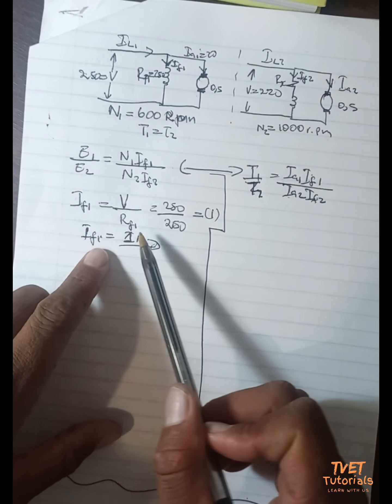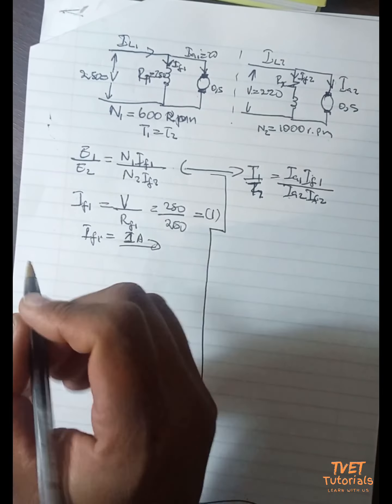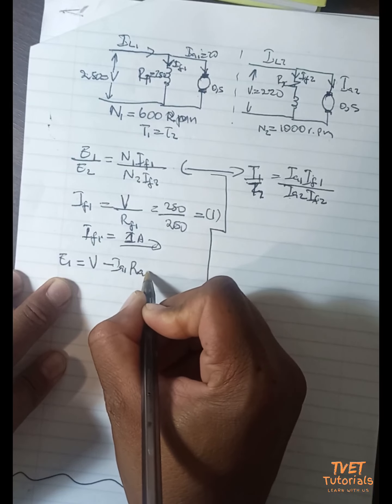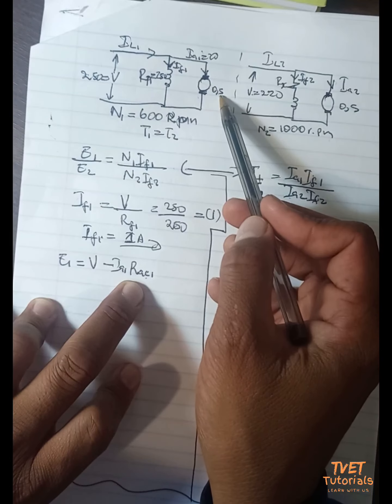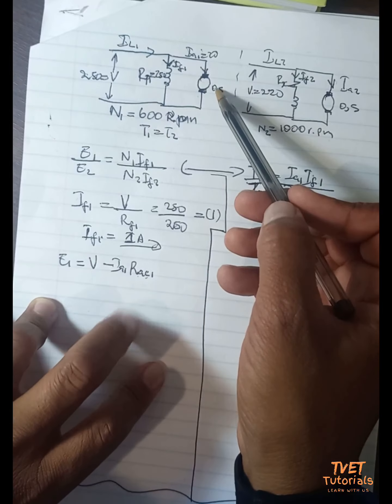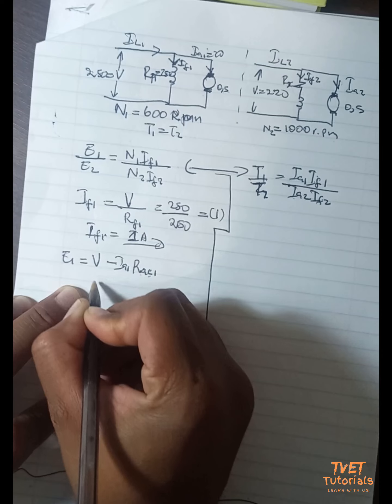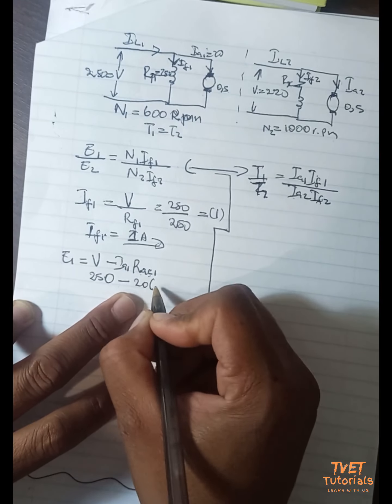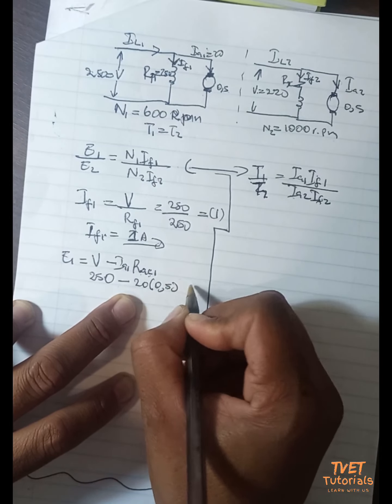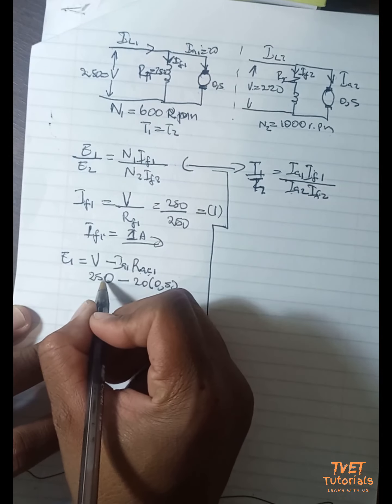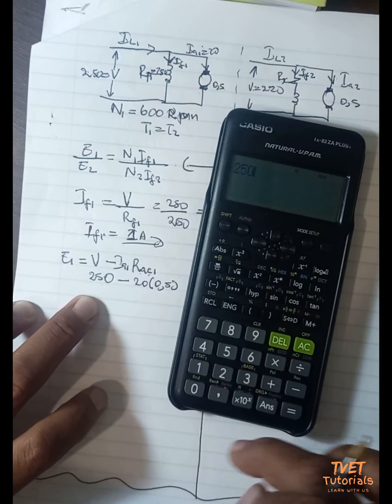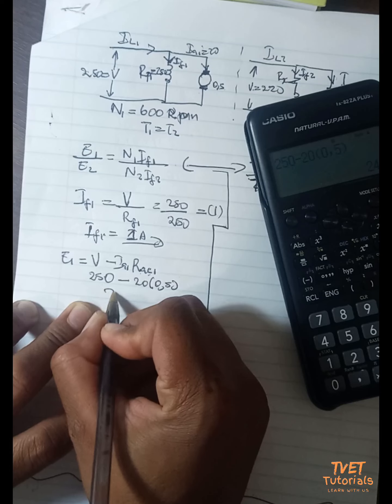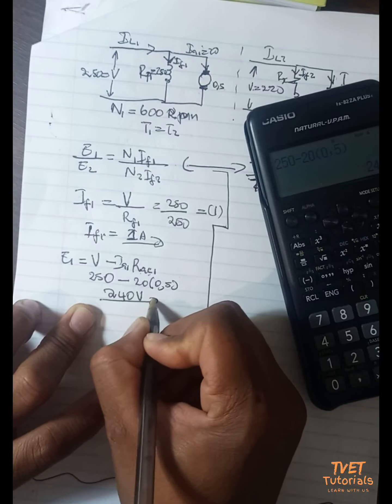We can also calculate E1. E1 equals V minus Ia1 multiplied by Rac1, where Rac is the armature circuit resistance. Substituting: E1 = 250 minus 20 times 0.5, which gives us E1 equals 240 volts.